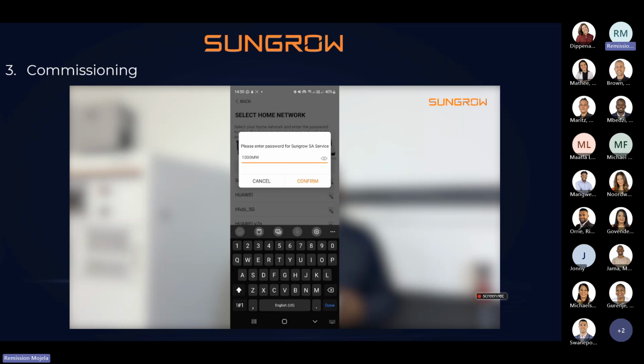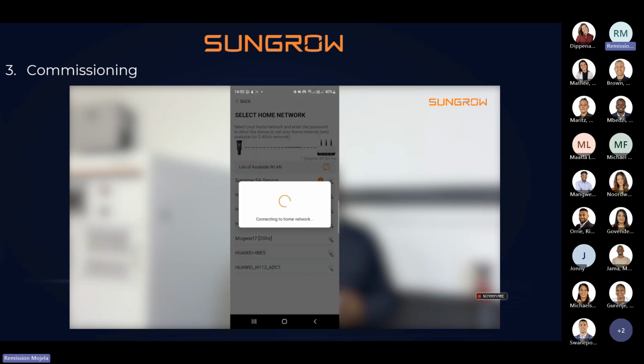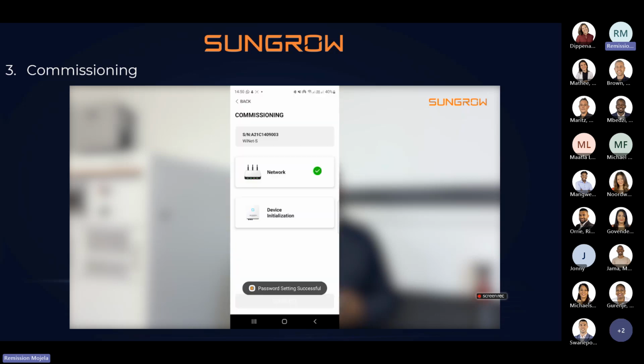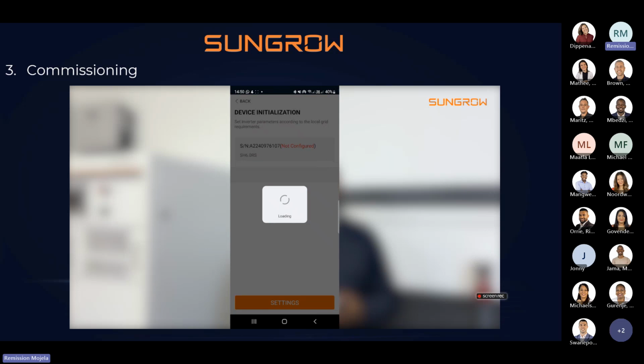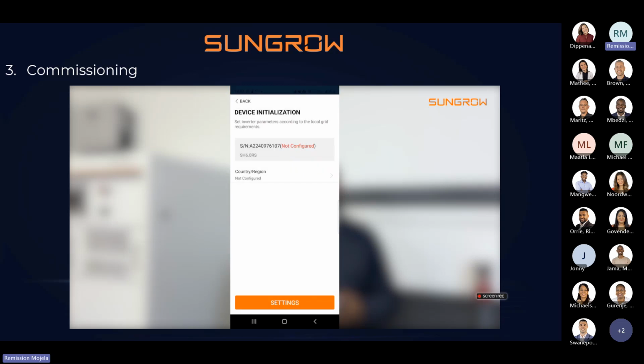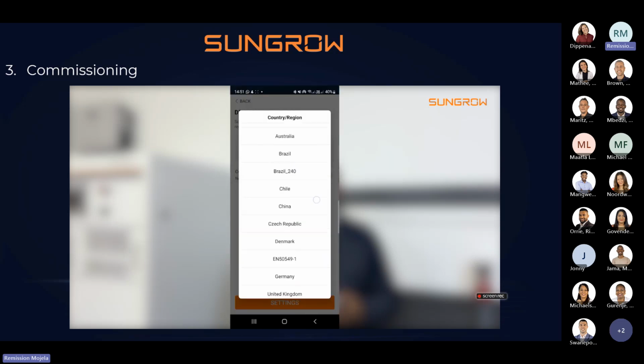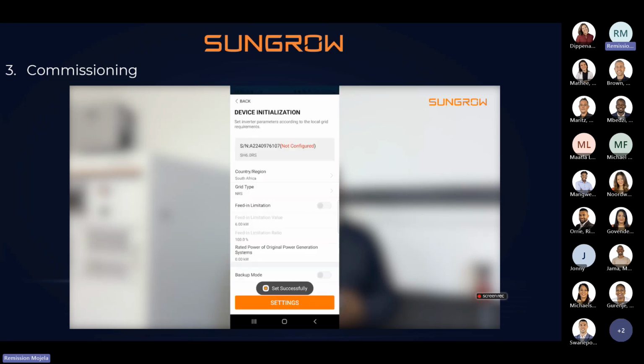After selecting the network, you put in the password, and it will connect as long as it's 4G. It can only connect up to 2.4 gigahertz, by the way. So 4G going down will work, but 5G has trouble connecting. The next part is device initialization, where you select the country code, and it will automatically select NRS as the grid type if you select South Africa.